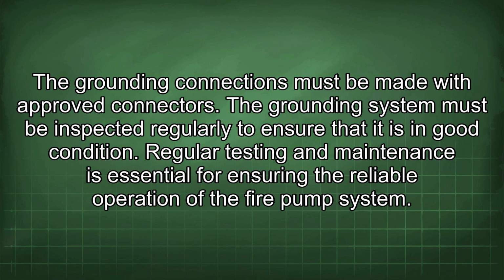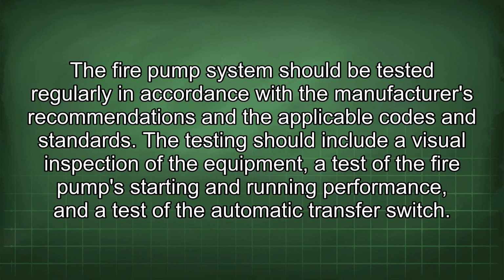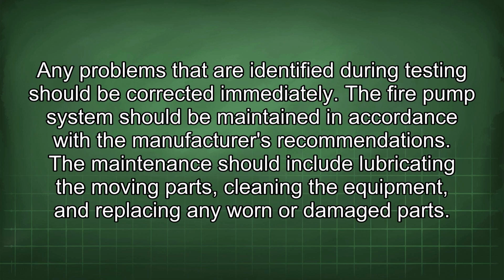Regular testing and maintenance is essential for ensuring the reliable operation of the fire pump system. The fire pump system should be tested regularly in accordance with the manufacturer's recommendations and the applicable codes and standards. The testing should include a visual inspection of the equipment, a test of the fire pump's starting and running performance, and a test of the automatic transfer switch. Any problems that are identified during testing should be corrected immediately. The fire pump system should be maintained in accordance with the manufacturer's recommendations. The maintenance should include lubricating the moving parts, cleaning the equipment, and replacing any worn or damaged parts.